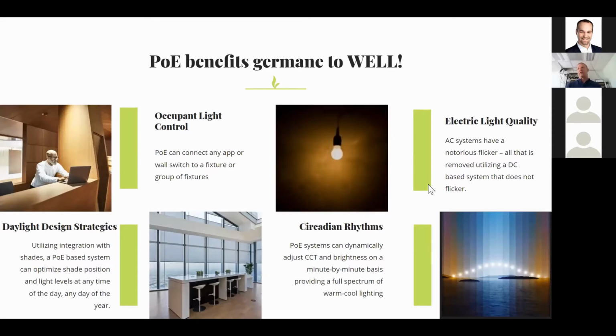Because we have a DC-based distribution system -- one of the things I found with AC systems is you can have a 60 hertz harmonic next to a 0 to 10 wire that causes a very slight flicker, or even worse, issues with a ballast for fluorescent lighting. Because we have DC-based distribution, that flicker phenomenon largely goes away.